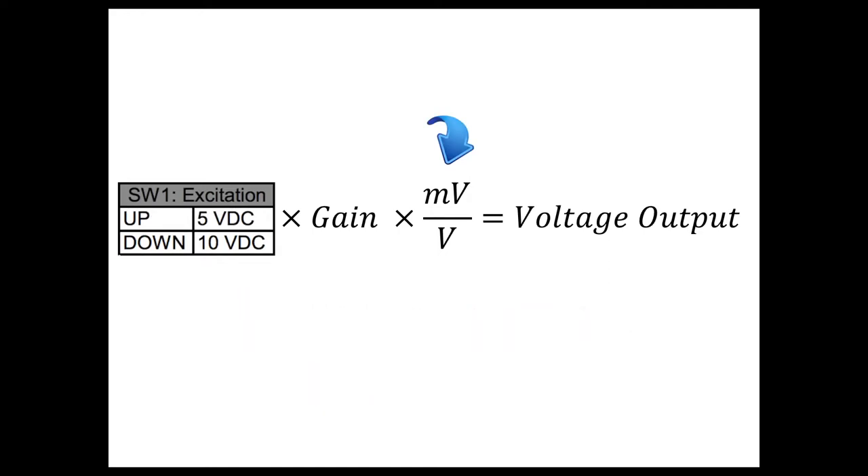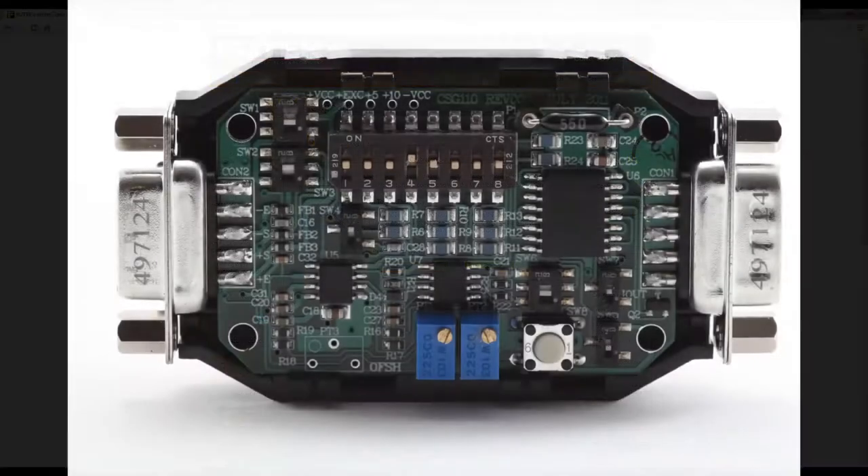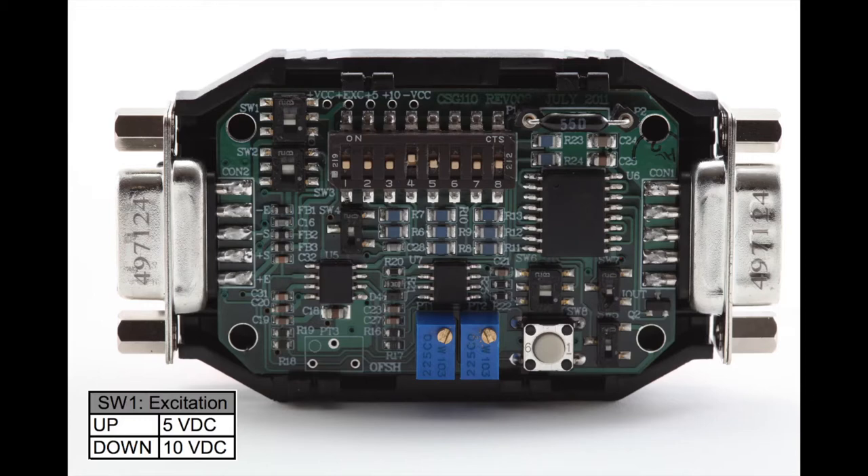The millivolt per volt output of your sensor can be found on its calibration certificate. You can find your sensor's calibration data on our Futek website. Simply enter in your sensor's 5-digit serial number and then click the green Submit button. There are two excitation levels available for the CSG110, controlled by dip switch 1, also known as the excitation dip switch. Using the dip switch, you can choose up for 5 VDC excitation or down for 10 VDC excitation. By default, the CSG110 comes with 10 VDC excitation.